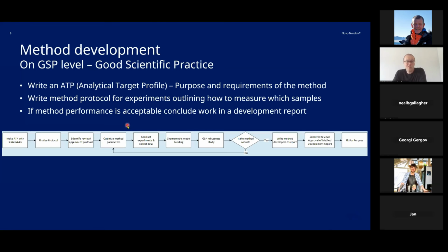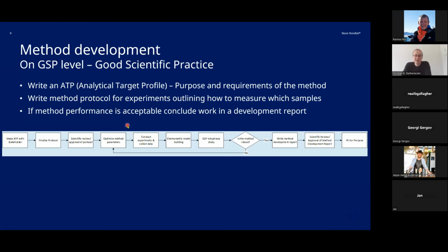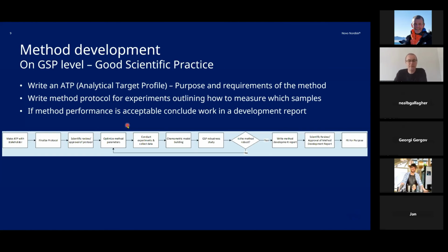And you need to incorporate how to mitigate instrument drift into your method by, for instance, taking a background, and you need to make sure that the background expires after the requested time period. So that is a requirement.